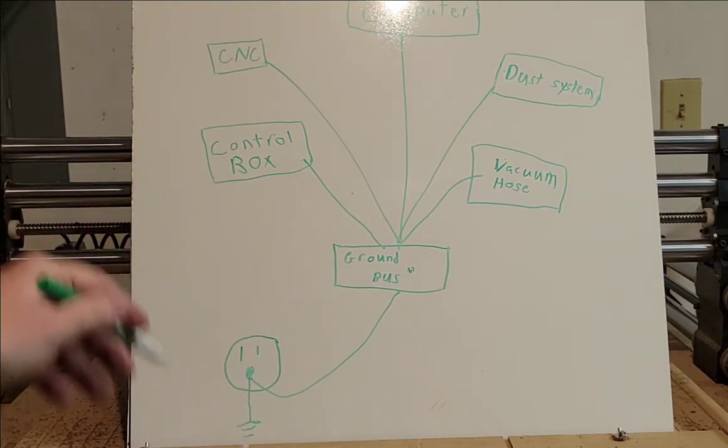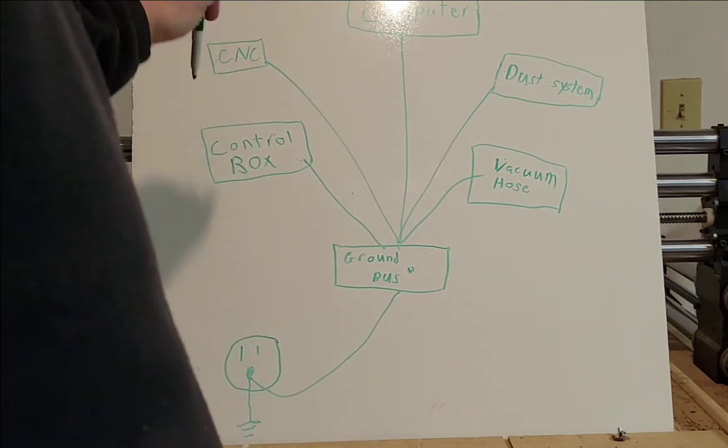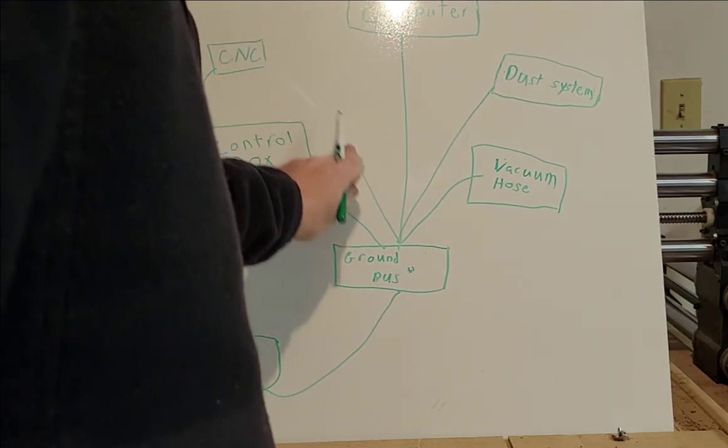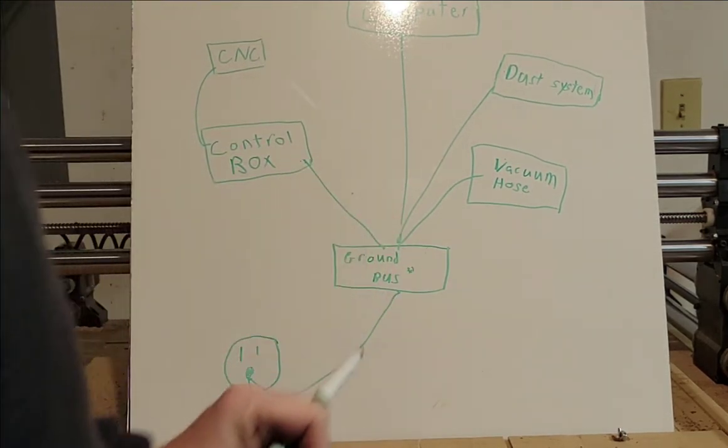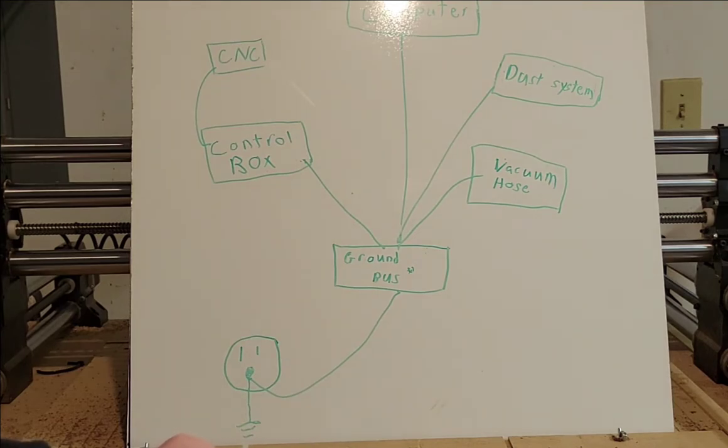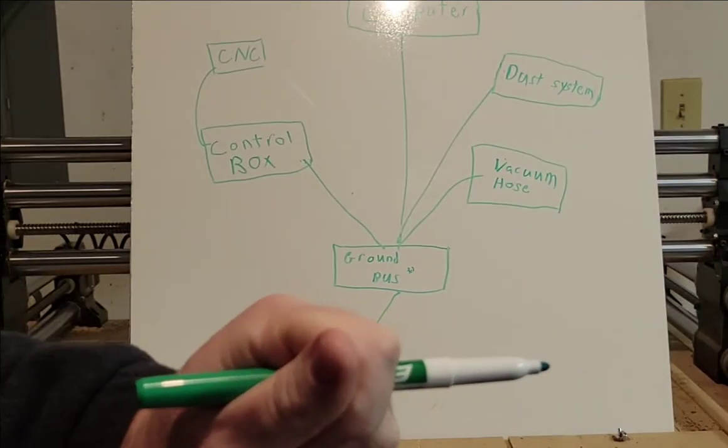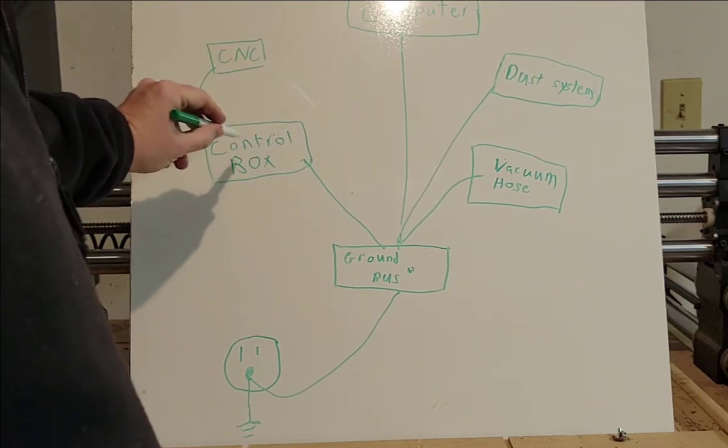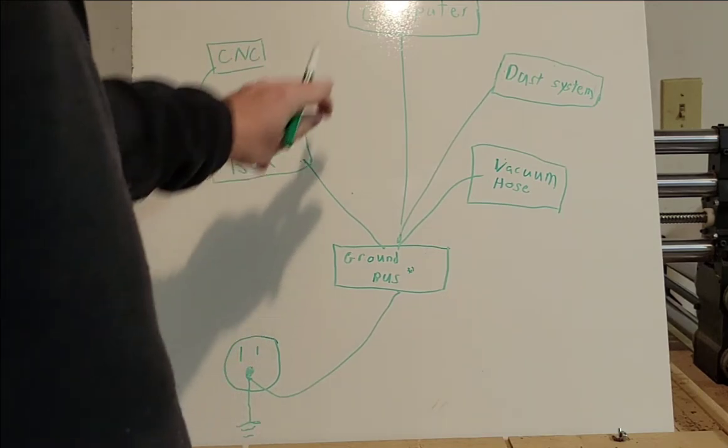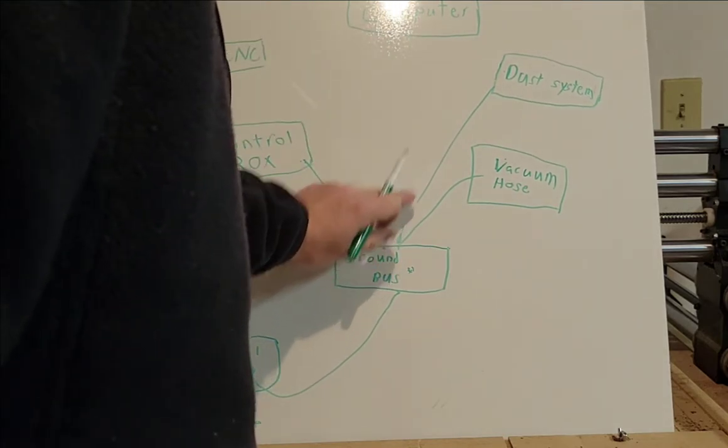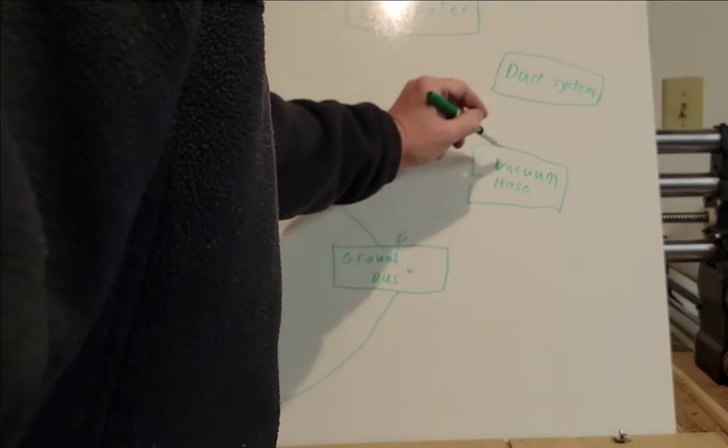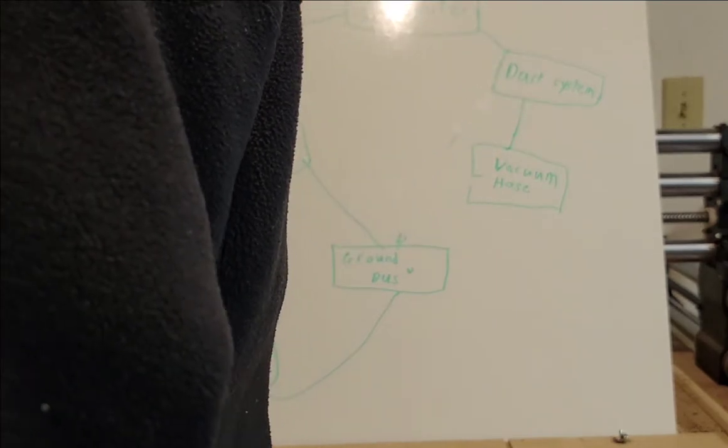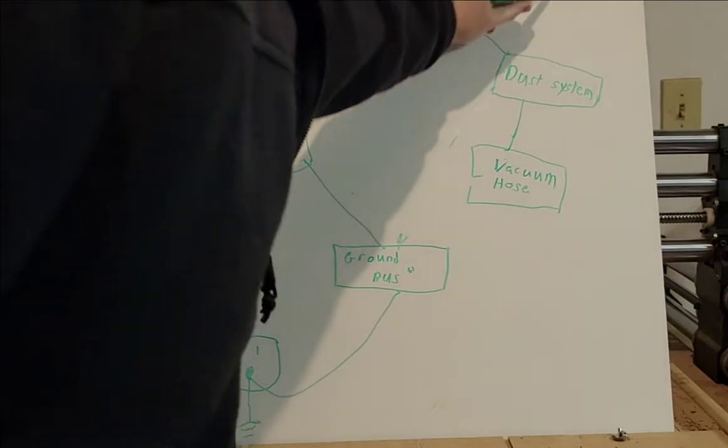...is they'll say 'oh well I need to ground the frame of my CNC' and so they'll ground to here and this will be here. That may or may not work because you don't know what's going on inside here. There's different grounding inside that control box. And what you can wind up with is you'll see people that'll do this and they'll have that tied to that, tied to that, and that is a big no no.